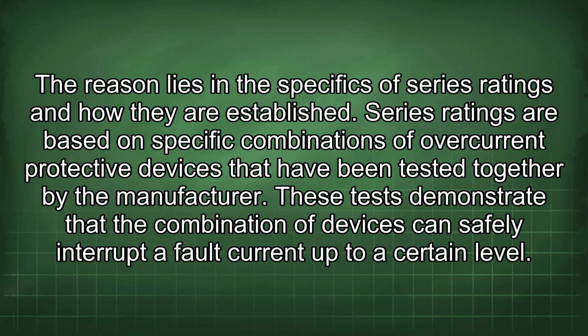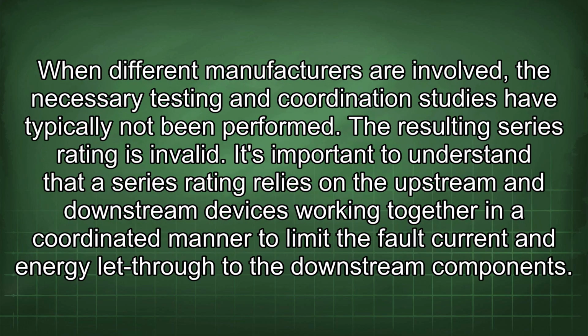Series ratings are based on specific combinations of overcurrent protective devices that have been tested together by the manufacturer. These tests demonstrate that the combination of devices can safely interrupt a fault current up to a certain level. When different manufacturers are involved, the necessary testing and coordination studies have typically not been performed. The resulting series rating is invalid.